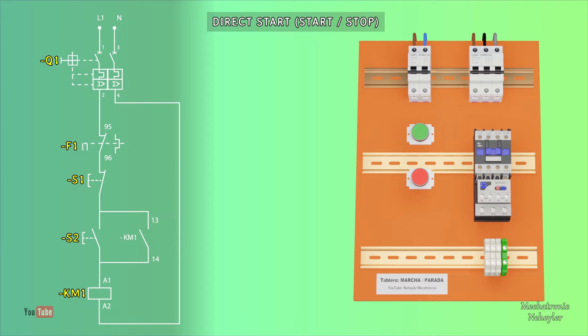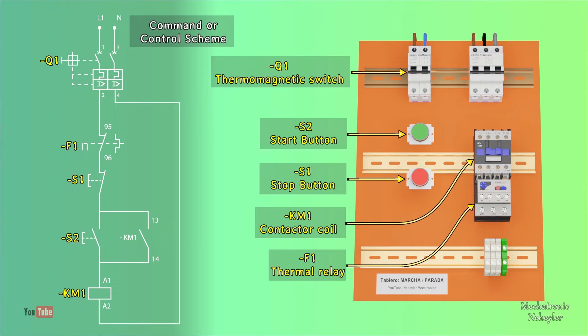Now let's see the elements that make up the control circuit. Q1 is a bipolar thermomagnetic switch responsible for putting the entire control part into service, in addition to providing protection to the conductive cables of the control circuit. S2 is a normally open button for start. S1 is a normally closed stop button.